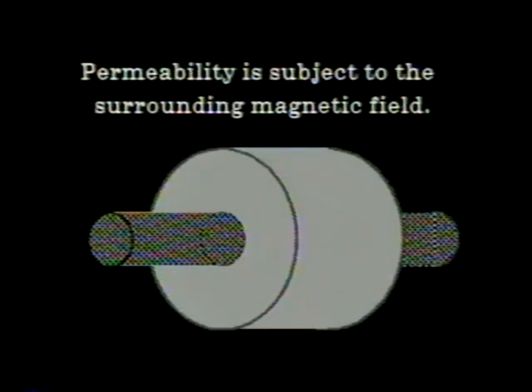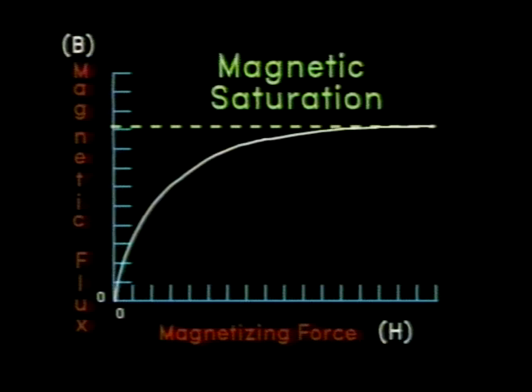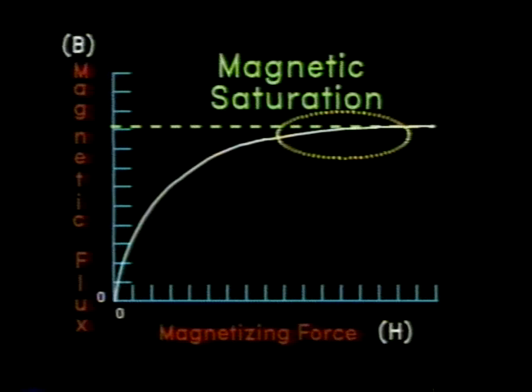Magnetic permeability is not constant for a given material; the permeability depends more upon the magnetic field acting upon it. Consider a magnetic steel bar placed in an encircling coil. As the coil current is increased, the magnetic field of the coil will also increase. The magnetic flux within the steel will increase rapidly at first, and then will tend to level off as the steel approaches magnetic saturation. This phenomenon is called the Barkhausen effect. When increases in the magnetizing force produce little or no change in the flux within the steel bar, the bar is magnetically saturated. When ferromagnetic materials are saturated, permeability becomes constant, and they may be inspected like other metals. Without magnetic saturation, ferromagnetic materials exhibit such a wide range of signals caused by permeability variation that signals produced by discontinuities or conductivity variations are masked. Permeability effects are most predominant at lower frequencies.